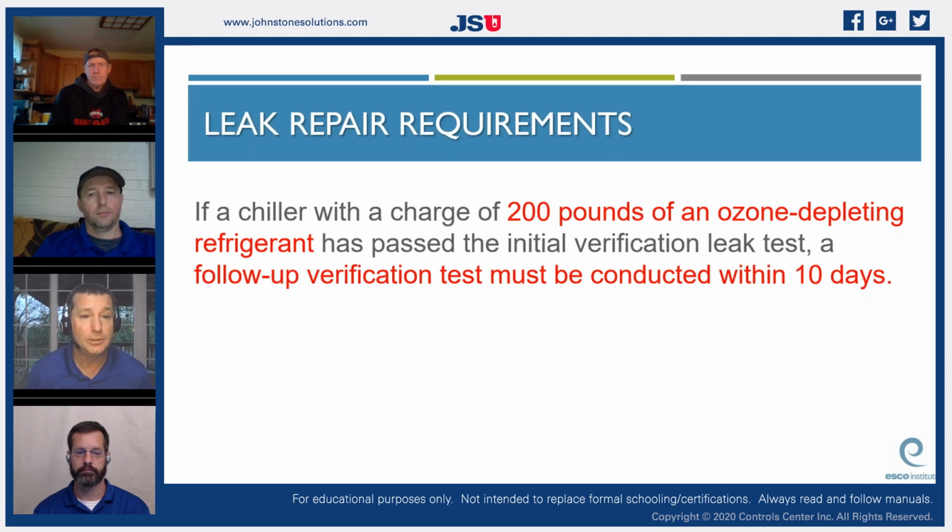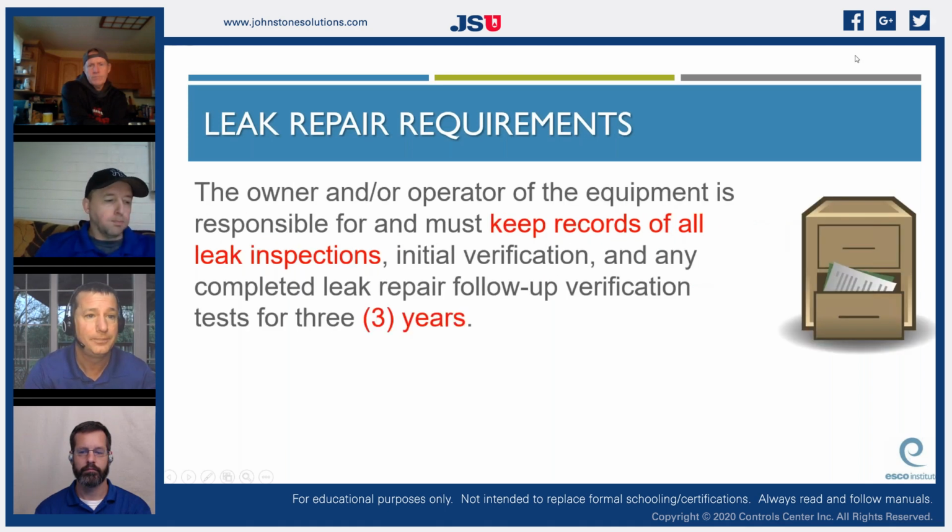That's it. If a chiller with a charge of 200 pounds of an ozone depleting refrigerant, remember chlorofluorocarbon or hydrochlorofluorocarbon, has passed the initial verification leak test, so we fixed our leak, a follow-up verification test must be conducted within 10 days. That means I have to come back again. Even though I have verified that I have fixed this leak, if it's an ozone depleting refrigerant, I still have to come back within 10 days and recheck my system that I just checked. The owner operator of the equipment is responsible and must keep records of all leak inspections, initial verifications, and any completed leak repair follow-up verifications, and keep those for a period of 3 years. So 3 years is going to be the key for all of our documentation.